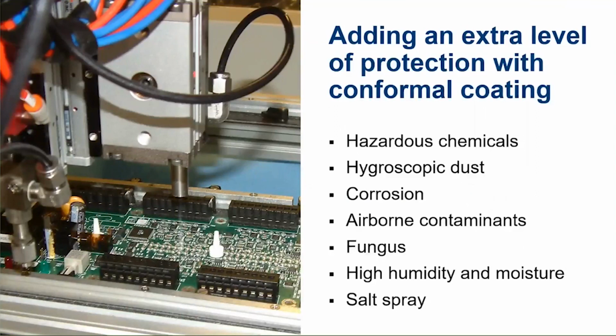It comes as a default selection in the product to do conformal coating over the entire product. This means that it's going to be covered with a form of plastic substance that protects against high humidity and moisture, salt spray, corrosive environments. I came from the paper industry prior to this. We had a lot of hydrogen sulfide. I know that in a lot of the water wells, there's corrosive agents in the chlorine area. And so having a product that has this kind of level of protection, so that if there is a leak or these types of corrosive gases in the cabinets, it still provides a very reliable solution to continue to operate through those extreme situations.